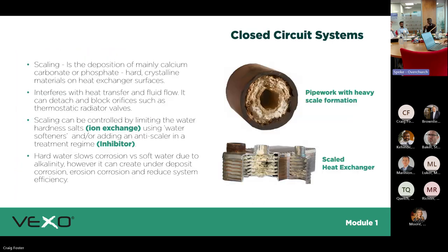Scaling is a massive problem — it depends on the area of the UK, but you can have a build-up of calcium within the system. Like tree rings, as calcium builds up layer by layer, and at operating temperatures of 60-70°C, the bottom layers bake and harden, making them harder to remove. I had a job in Canary Wharf at a bank where they removed their pipework and found the capacity was reduced to about a quarter — that's in a data centre and mission-critical environment — all from untreated water or water untreated for scale.